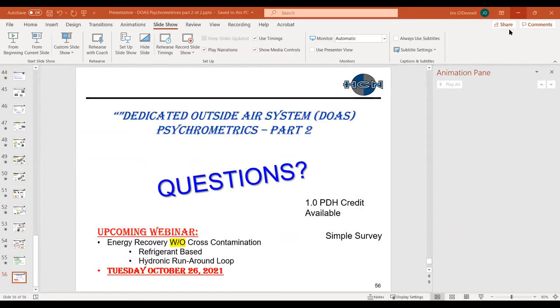Question: How low a temperature source for regen can you go? In the applications I've done, I haven't seen anything below 180 degrees Fahrenheit for regeneration — though that's just one person's experience. A comment from Jim McCoy, who has done many desiccant jobs, notes that 248 to 284 degrees are typical regen temperatures.